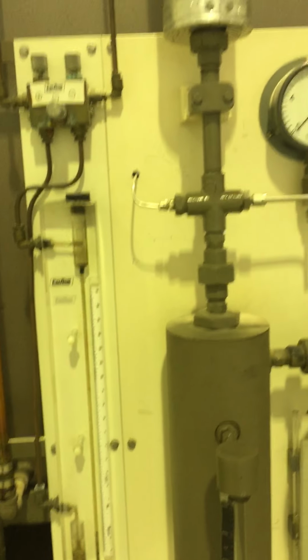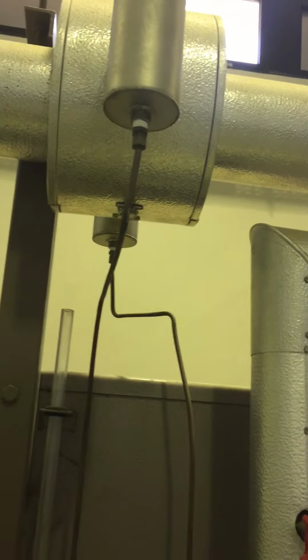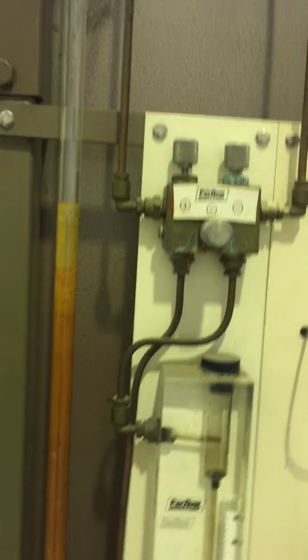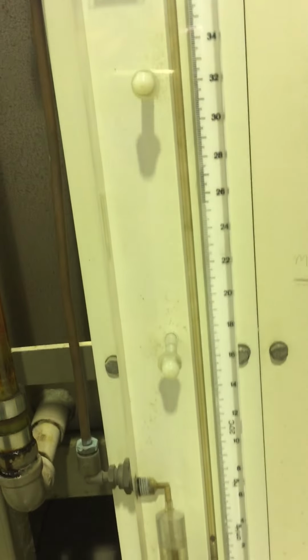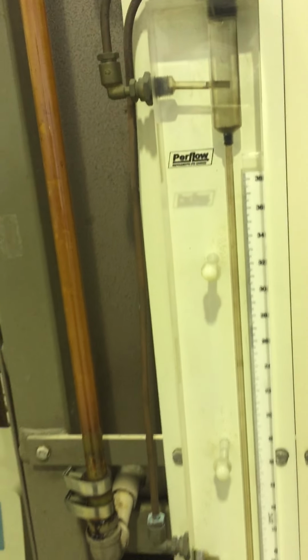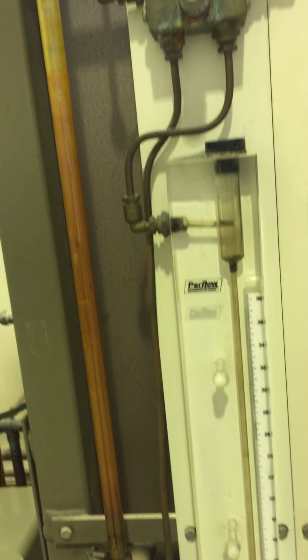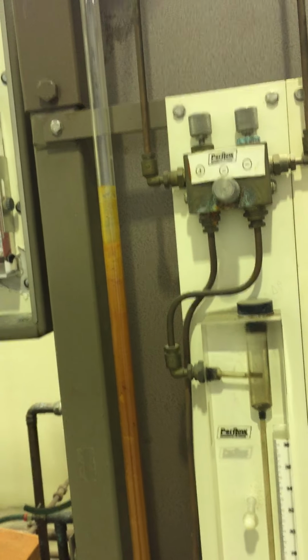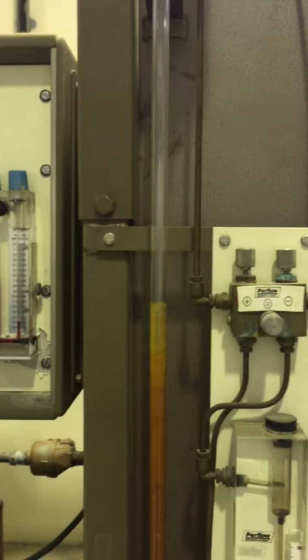For the steam flow measurement, of course, we have the saturated steam supply. It will pass to the orifice in here. So inside here there's an orifice, and across the orifice we have the pressure drop. We measure the pressure drop delta P using this manometer in millimeter mercury, and using the equation for the orifice, which is mass flow rate equal to a constant times the square root of density times delta P across the orifice. This will give us the mass flow rate of steam through an orifice.